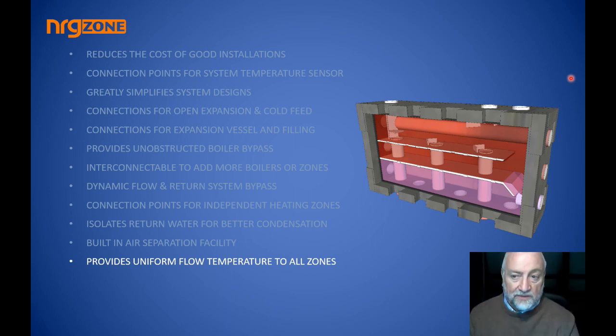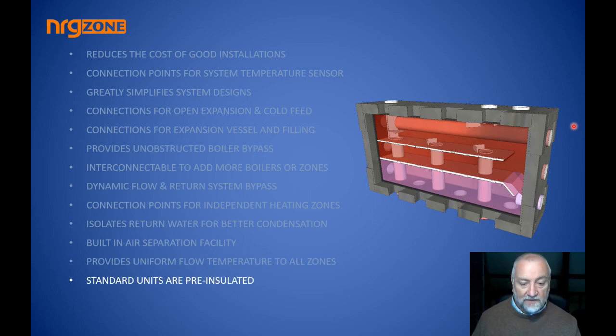I said to you that you come across a lot of systems where the flow from the boiler can be undersized, and people like Caleffi and Taco, who have different drawings, all say you must have a proper header size, you must allow for the volume to pass to reach all the different zones. With this scenario, we've got an extraordinarily large area inside, even for a small domestic situation. We've got an extremely large chamber on the flow and on the return that gets rid of all the hassles with not having uniform flow to every circuit. So problem solved.